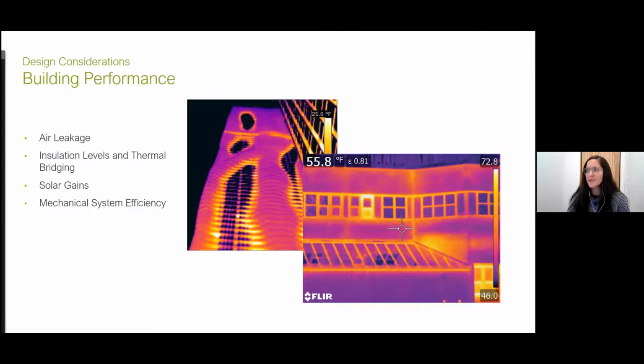But with geothermal, we had to take a close look at it, because if your building is not performing as optimally as it can, the scale of your system increases and the demand you need to make up for increases, which means your well sizes increase and your geothermal field increases. That's where the biggest cost associated with geothermal is. The system itself within the building is just some pipes, pumps, and HVAC units, which are already in the units anyway. It's really drilling the bore field that creates the biggest cost increase.